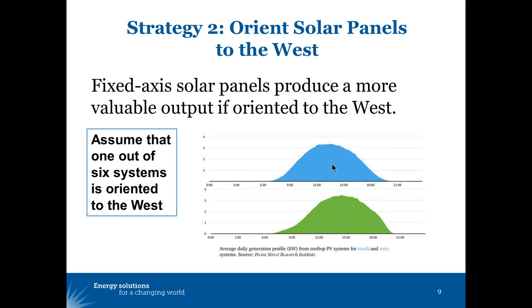Now, the next strategy is to orient solar panels to the west. Most solar panels installed on rooftops are fixed-axis panels, so they're racked in one direction or another, most often south. But if we were able to orient 1 out of 6 systems to the west, we would shift the production of those to start later in the morning and go longer in the afternoon. This line here shows what happens at 6 o'clock, oriented to the south, in blue.